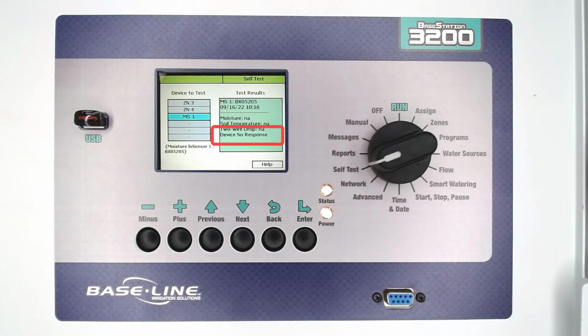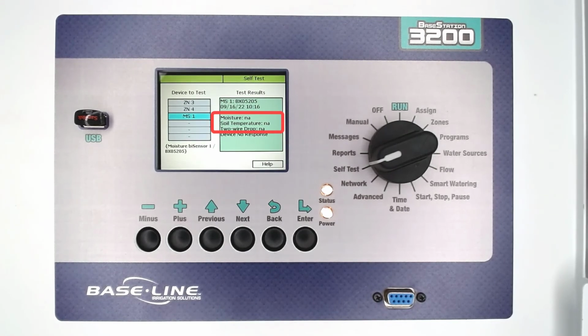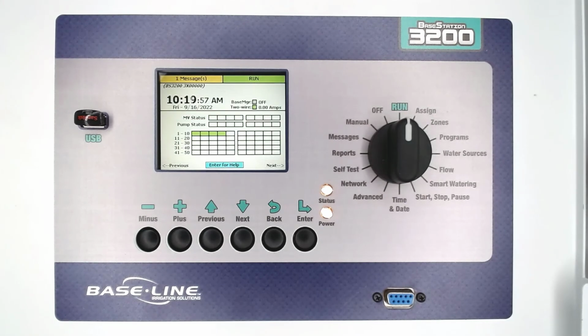Device No Response indicates that the controller can't communicate with this moisture sensor. Moisture was shown as not applicable, and soil temperature was also shown as not applicable, confirming a communication issue. With this information, start looking for a problem with the sensor or the connecting wire path. These next steps are about the process of elimination, either the sensor or the wire path.